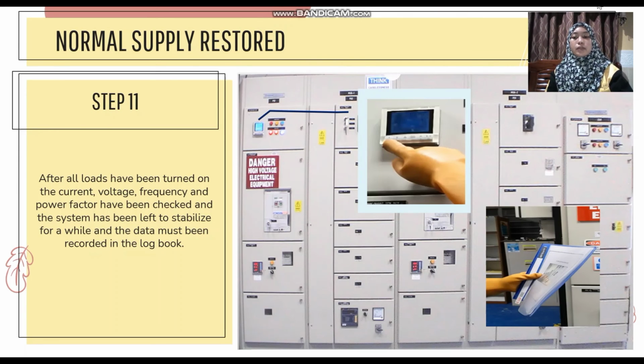So step 11: after all loads have been turned on, the current, voltage, frequency, and also the power factor must be checked here. So we will check all the parameters, and if okay, we will give some time for our system to stabilize, and the data of the voltage, current, and so on will be recorded into the logbook.